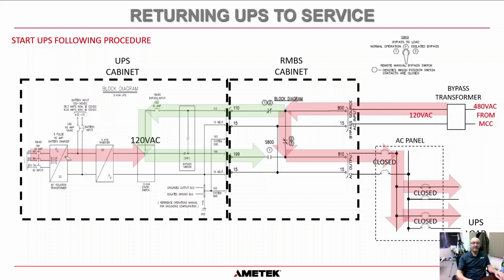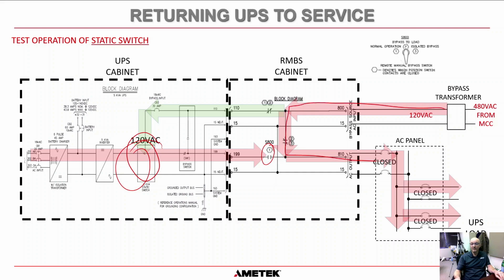At this point, I mentioned earlier that in position 2 we can test the static switch. So that's what we're going to do next. We can press inverter to load, bypass to load, and make sure that it transfers within the UPS itself. Now remember, this contact here is open, so it's not going to do anything to the load circuits. The load circuits are still powered through this contact here, but we can test the operation of the UPS when we are in position 2.